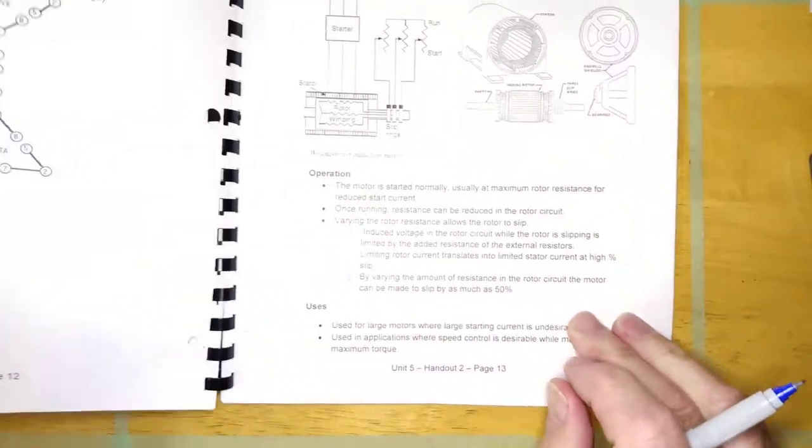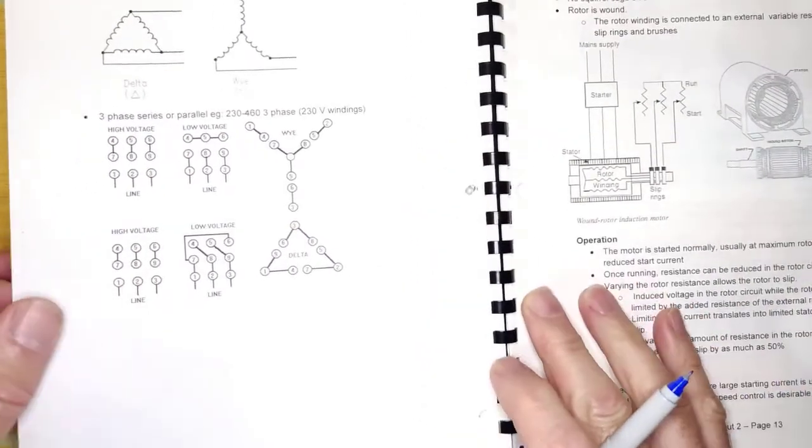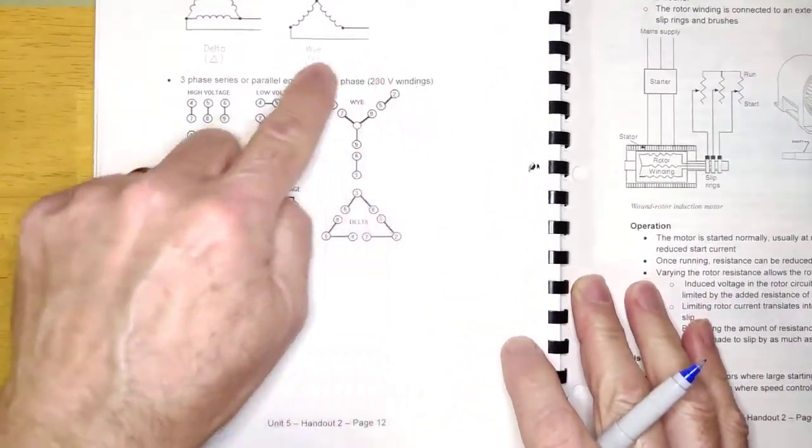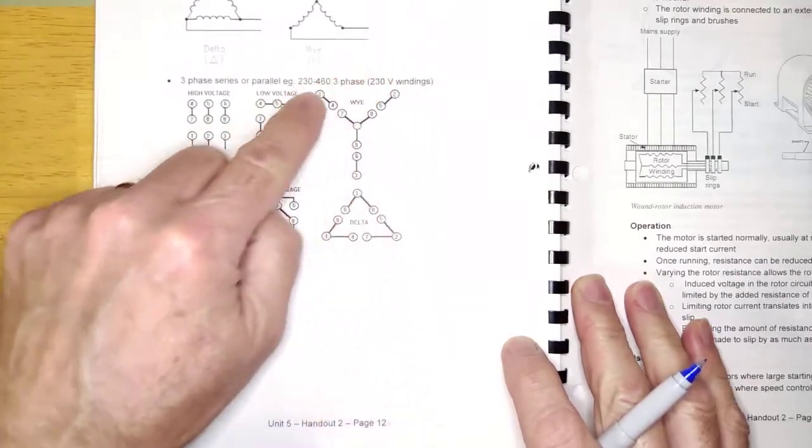And so I don't care if you connect the motor high voltage or low voltage, the windings themselves are going to get their rated voltage, which is 115 volts. This machine will have 115 volt windings. And those windings will get 115 volts, no matter if you connect it to 230 or 115, as long as you've wired it correctly.